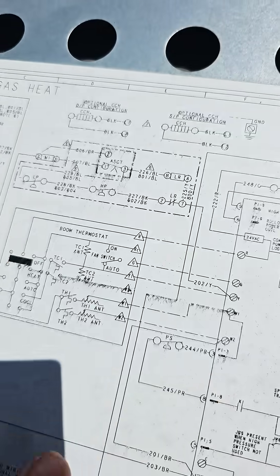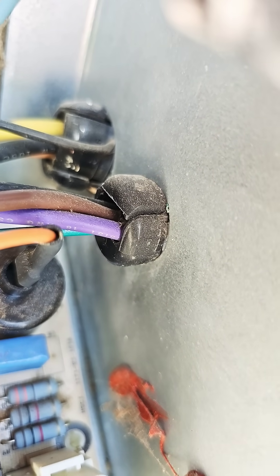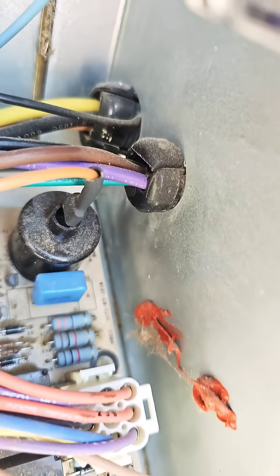So let's see where we're losing the signal. Here's the relay the pressure switches run through — and look at this. Looks like the wire has been cut. Let's fix that and see if it comes on.